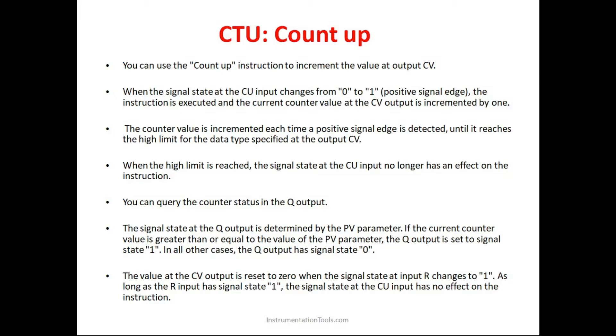So it is counting the number of input pulses. At a certain point, the current value will reach the preset value PV, which we set in the counter. For example, if we set the preset value as 5, when we have given 5 pulses the current value equals the preset value. Whenever the current value is greater than or equal to the preset value, the output will be in the high state.